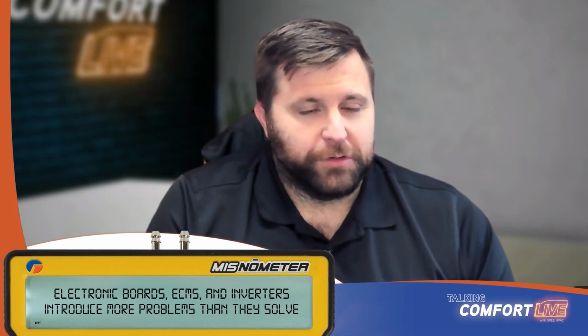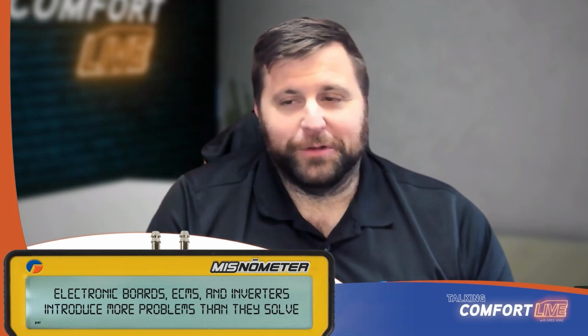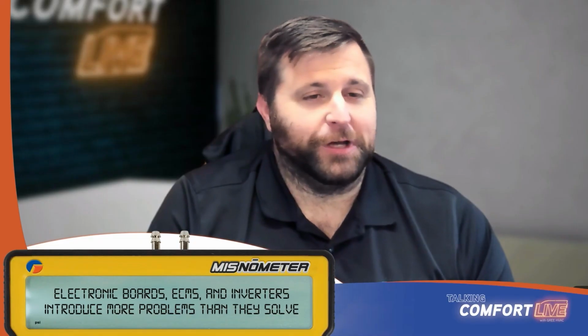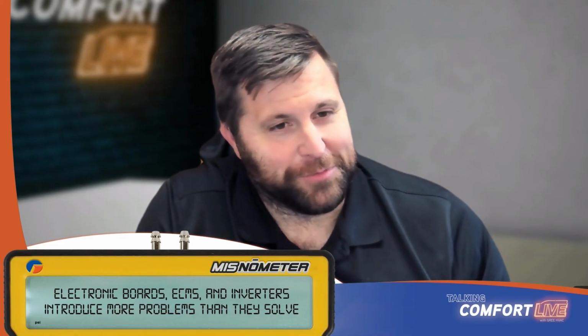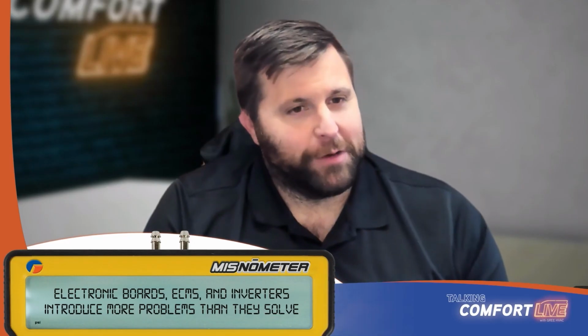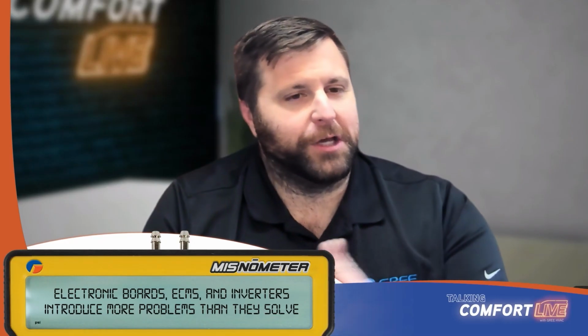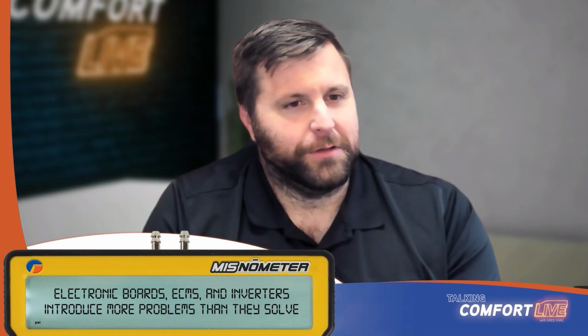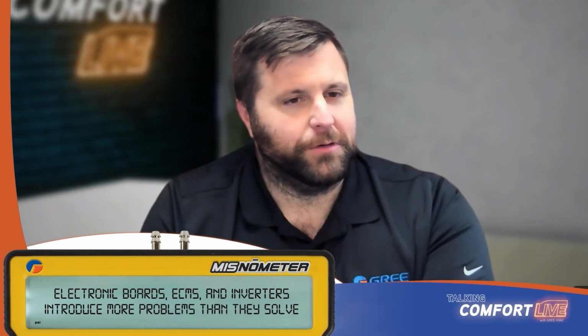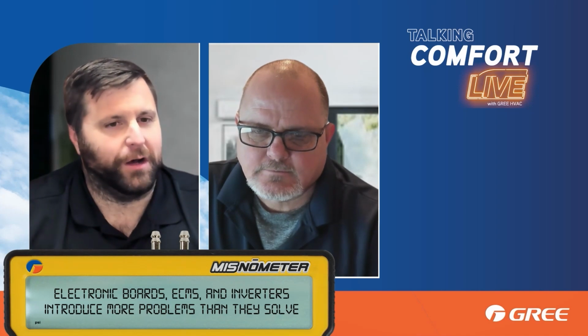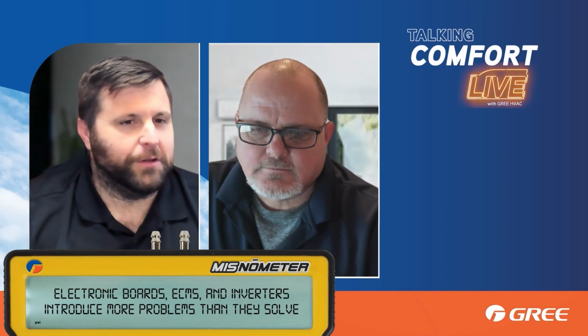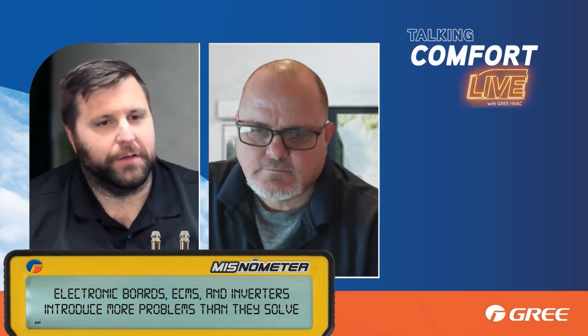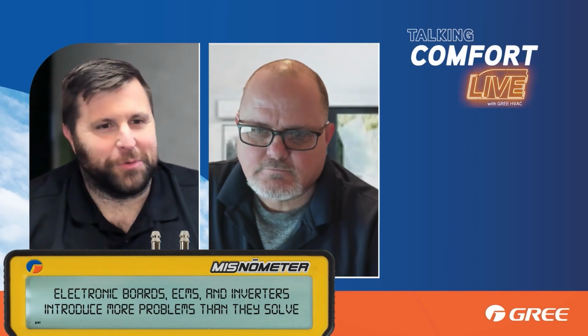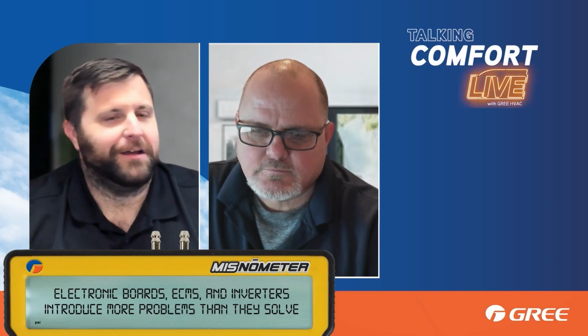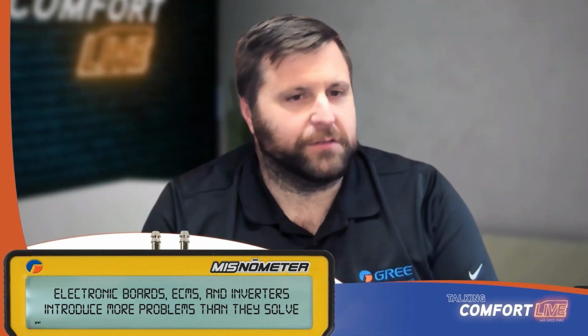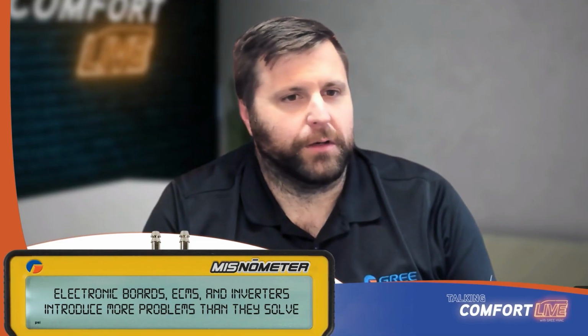Well, mini split manufacturers have known that for decades now. And what can happen, like if you've got a mini split sitting on a rooftop somewhere, just because you don't have a call for cooling doesn't mean something's not going to happen, because we've got a built-in sensor on the inverter board, and the fan motor can come on and cool that inverter board off. So even after you run a cycle, if it's still hot, it'll run that fan motor to cool it off. I mean, these are lessons that were learned years ago, and in this case, this very high dollar, very brand new system, top of the line and all that, they're discovering something that, again, is a lesson that's 30 years old or more at this point.